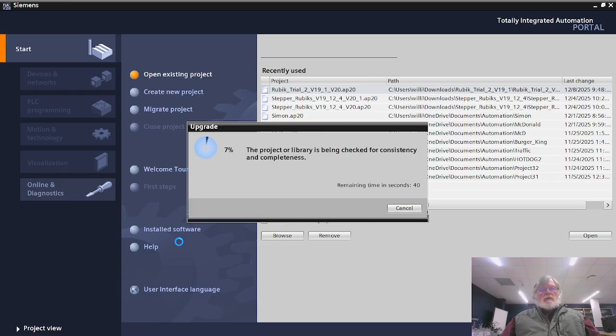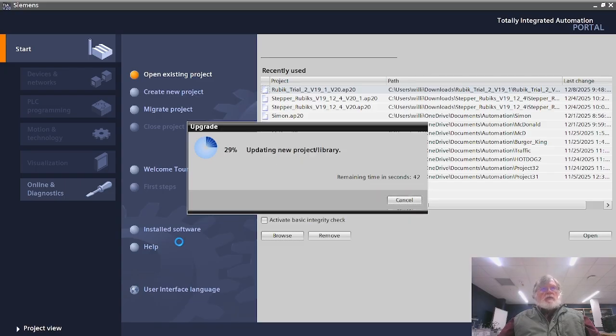But this is where we remember from Lab 7, if you did it, that we had to do the steps where we compiled but didn't download the PLC program. We went over and compiled the HMI program. The reason for that is because you have to have the same certificate, which is the date stamp, for each of them before you can download. So if you were to do the compile and then download without compiling the HMI program, it wouldn't download.